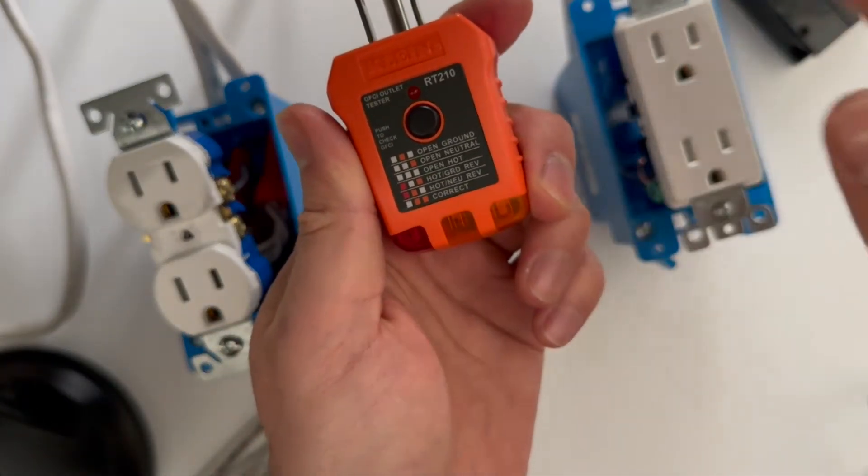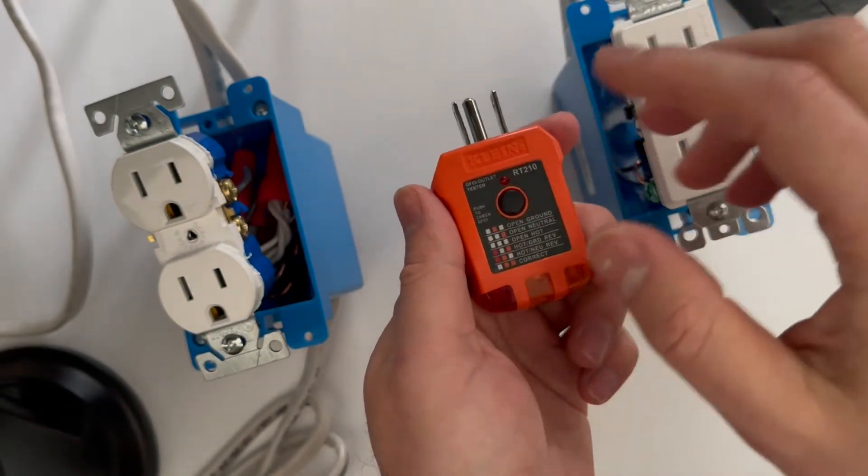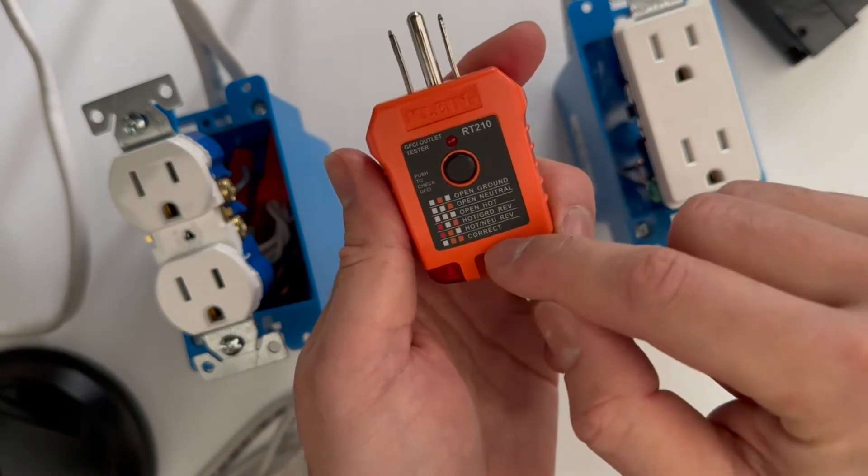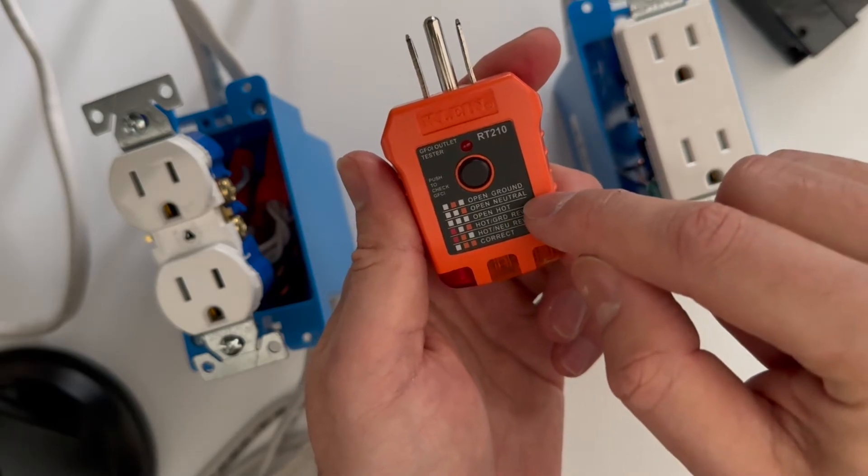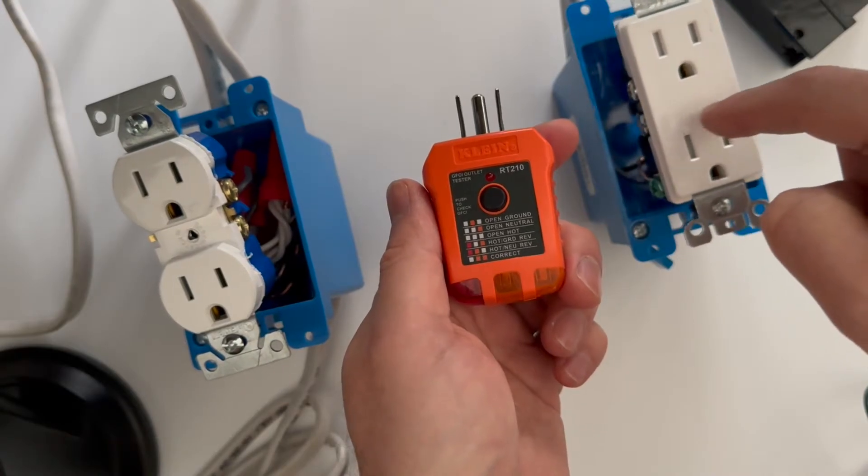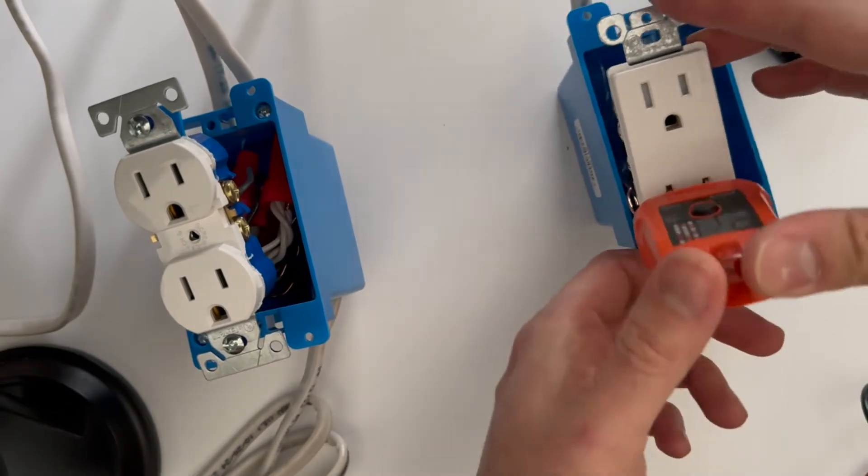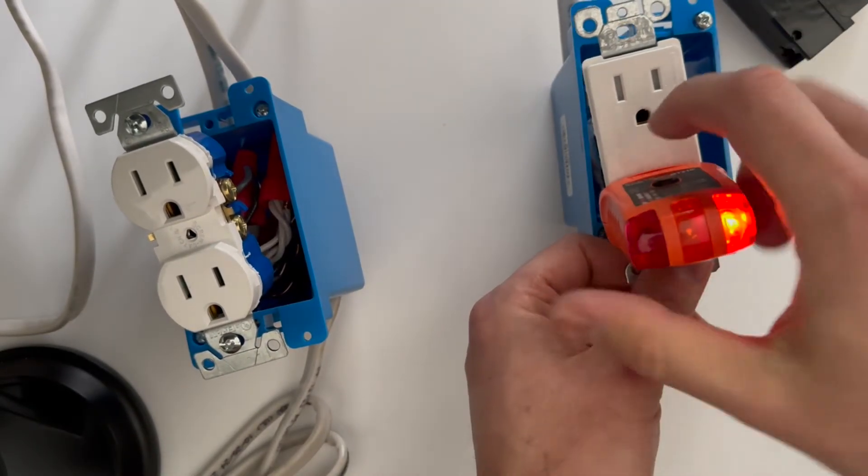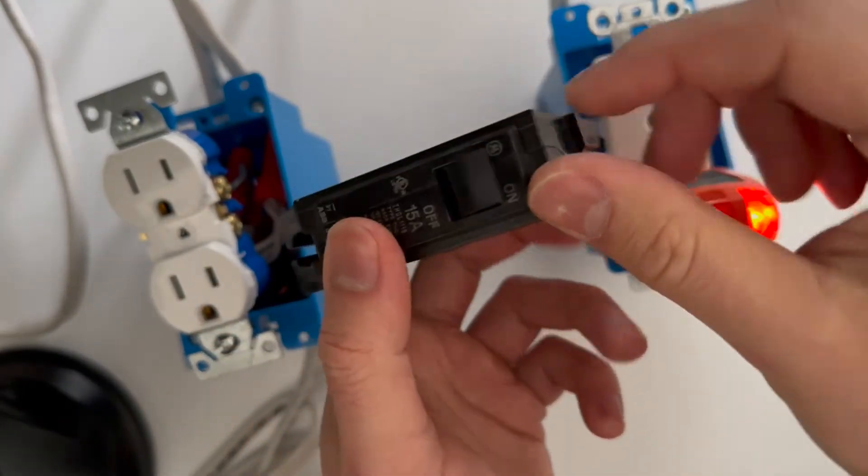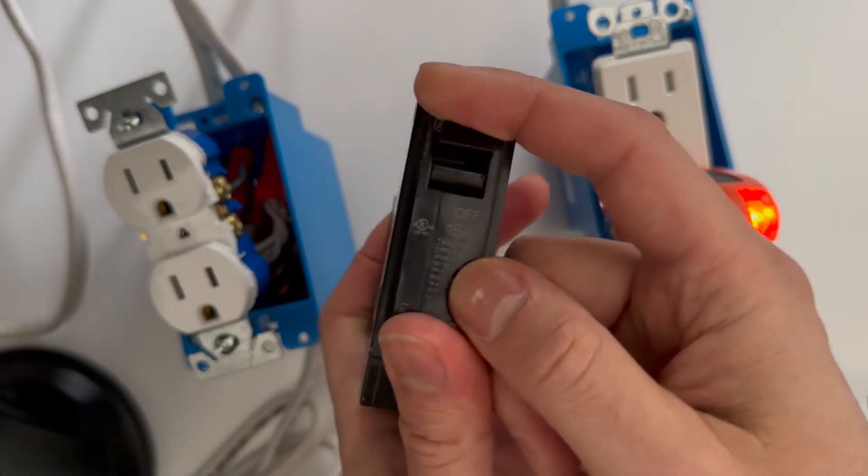If your circuit has been working just fine and all of a sudden you have this situation where you have hot ground reversed and open neutral, you're not necessarily looking for a problem in the outlet that's testing this way because you might have many outlets. If it's a 15 amp circuit breaker, you will have around eight devices.